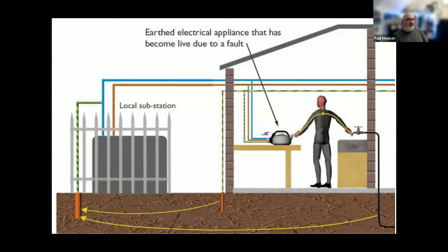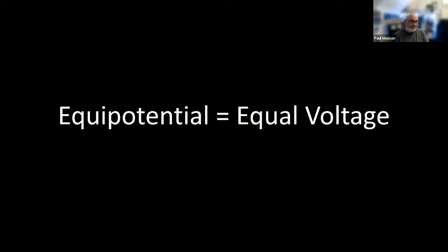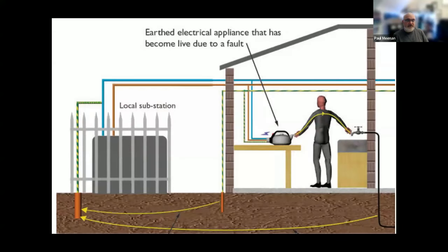So if you look here, you have an installation with an electrical appliance that's become live due to a fault, and that person there could be touching a water pipe which is brought in from the outside. Now, the kettle is an exposed conductive part. It's exposed metalwork, forms part of the installation, is generally expected not to be live, but could become live. The extraneous conductive part is very similar, but it's generally considered zero, and it could become live. It could also help form a path. As you can see, the path of the fault could go through the gentleman who is undergoing that fault condition. Now, simply put, equipotential means equal voltage. So if I bond that water pipe as it enters my building, in theory, I should have an equal voltage.